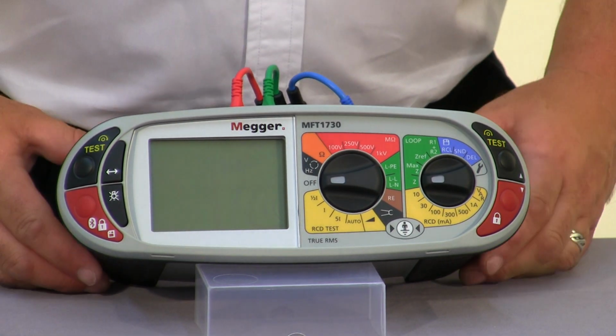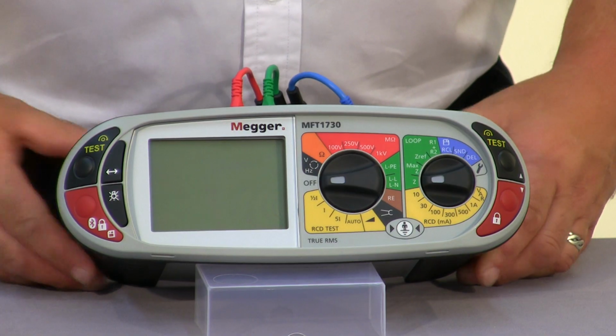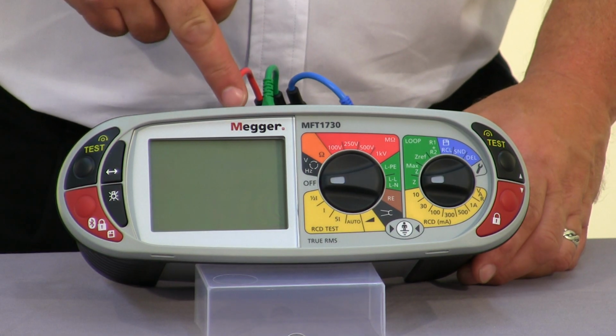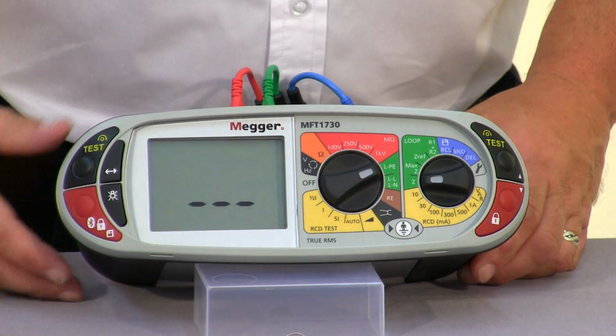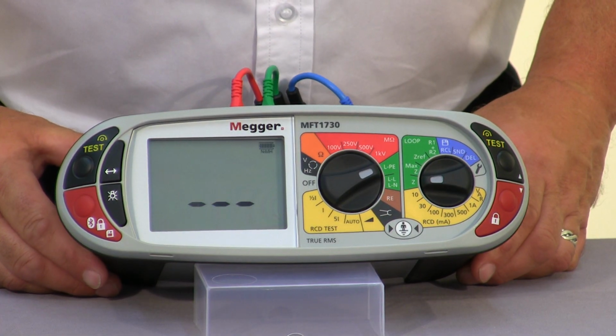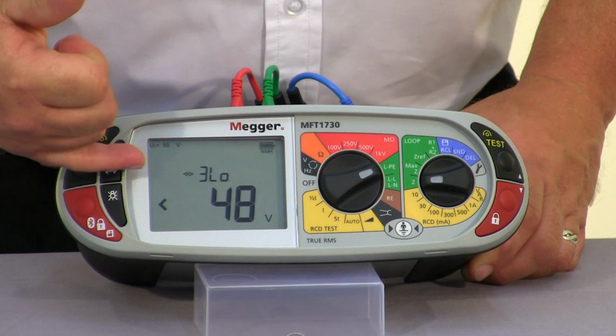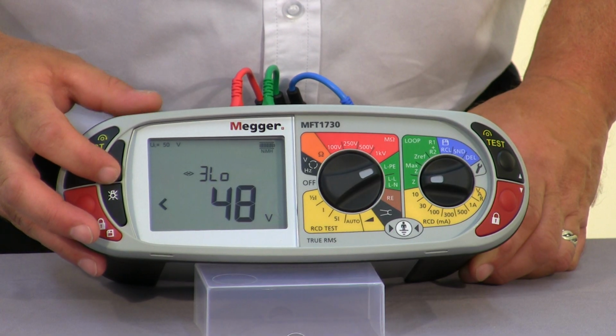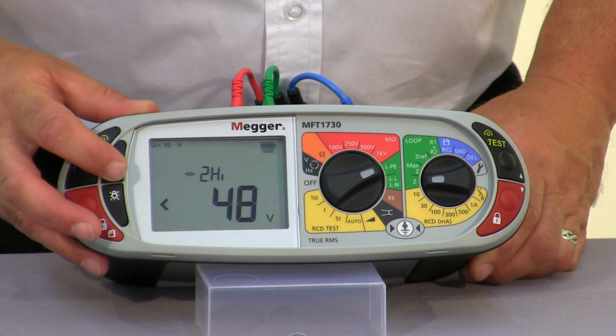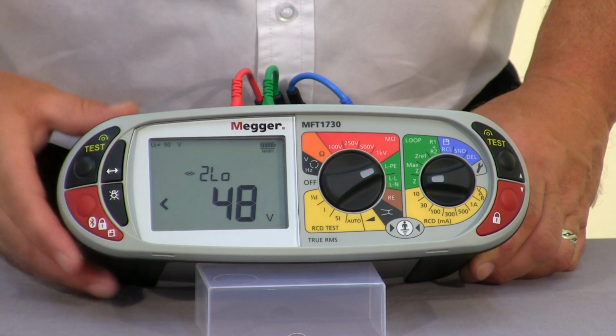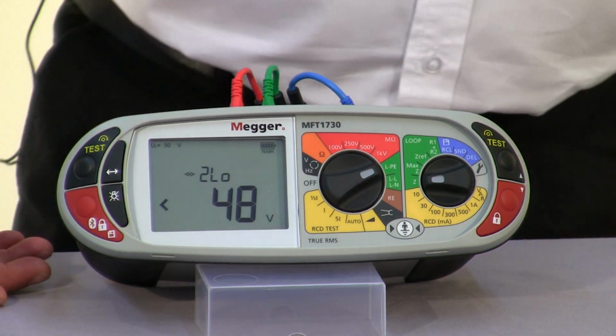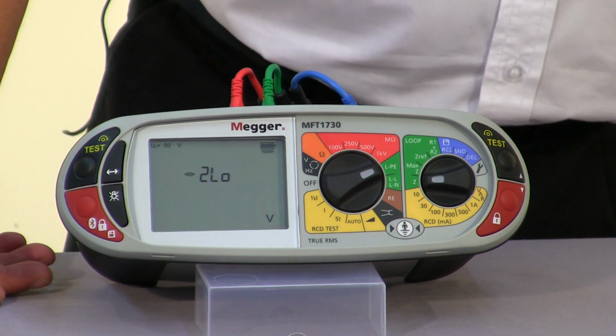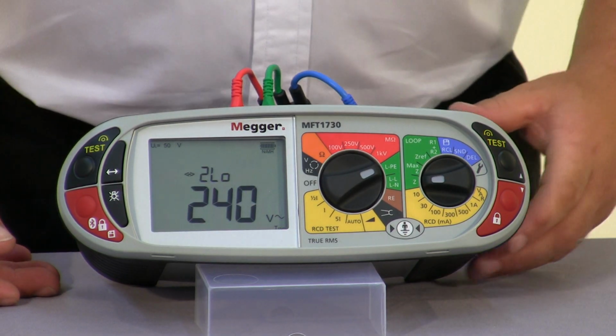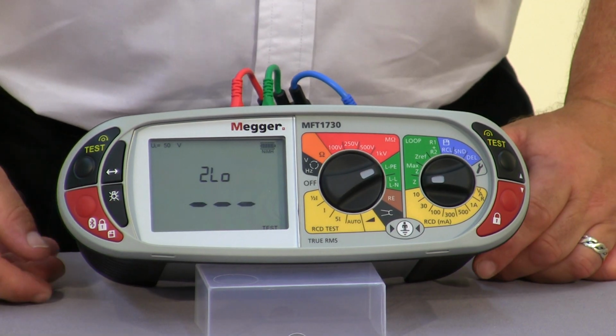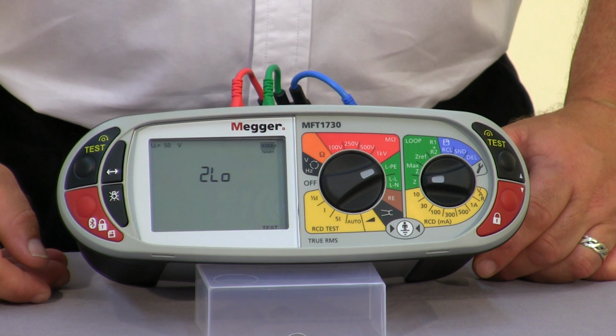So now we'll run through a standard two-wire no-trip test. So you'll see now that we only have the live and the neutral connection, and we go to our LPE setting, and on the screen obviously we have to cycle through from our default, which is our three-wire, to select two high and then down to our two low.